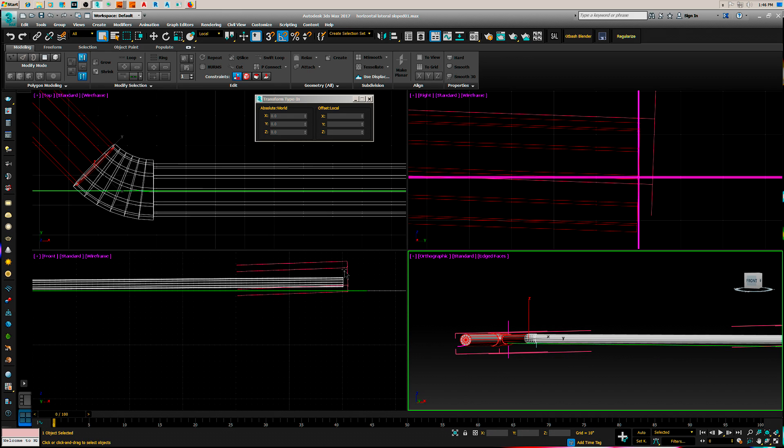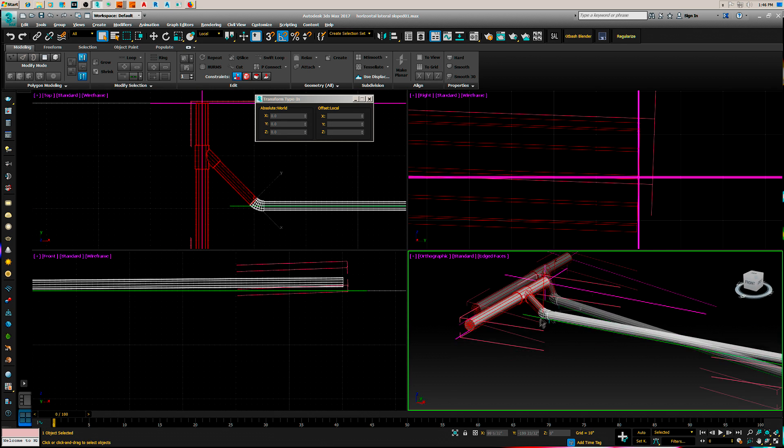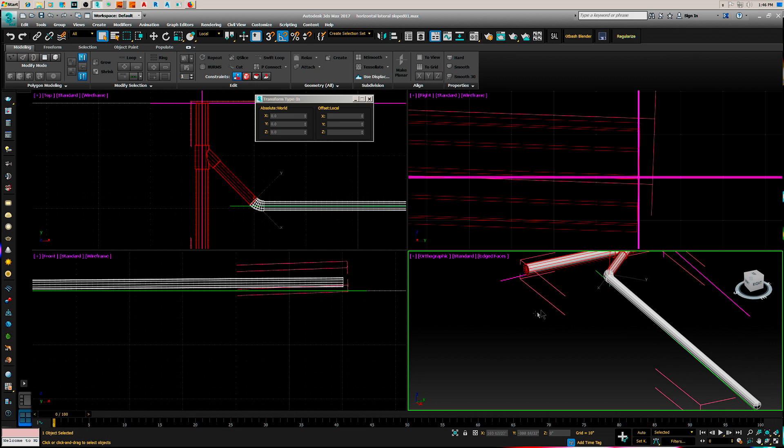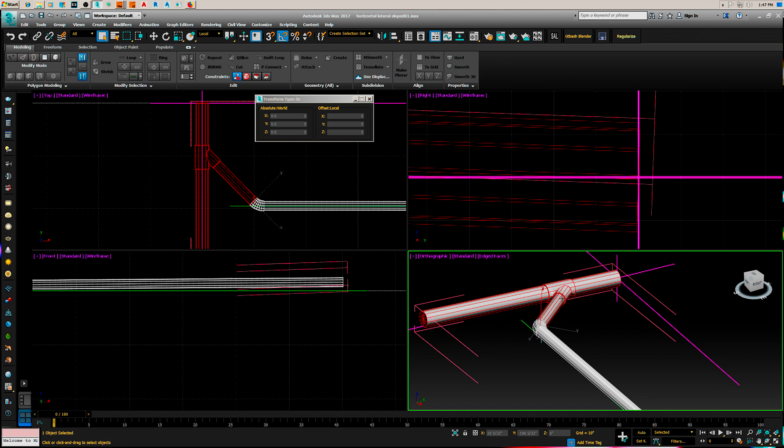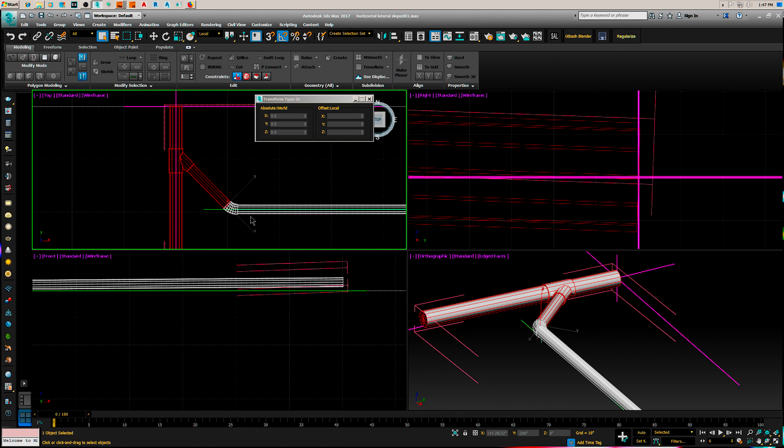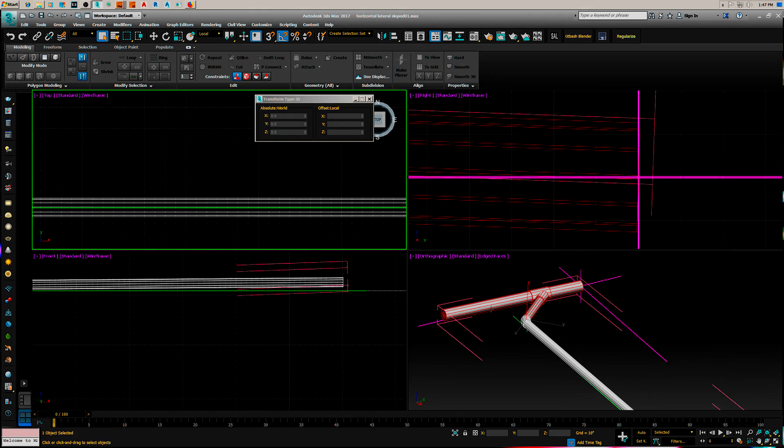Anyway, this is the proper way to do it. So what we want to take away from this is we want to rotate our fitting to match the slope of our branch. And we want to drag a pipe out from our lateral stop it and then pick it up again and drag a new line with our slope on it, which is essentially rotating this fitting to do what I did over here. Rotate it to get a parallel or perpendicular to our main.